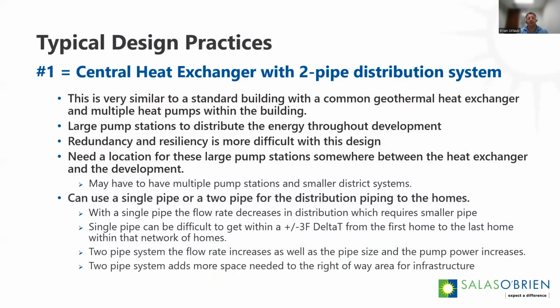I'm sure there's other ways you could do it, but from what we've seen, really to keep costs in check, take up as little room as possible with piping, and try to get piping integrated with other infrastructure, whether it's in the right of ways and streets, and then keeping an eye on that pump horsepower, making sure that we're not over designing a system that has so much pump horsepower that we're negating all the efficiencies we've gained by going with geothermal. So the first system here is what we call a two-pipe distribution.